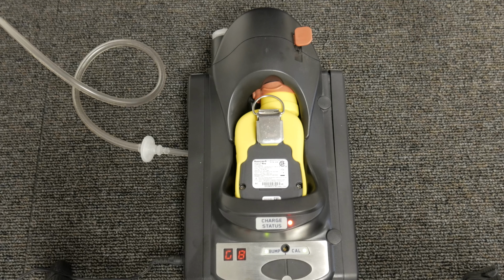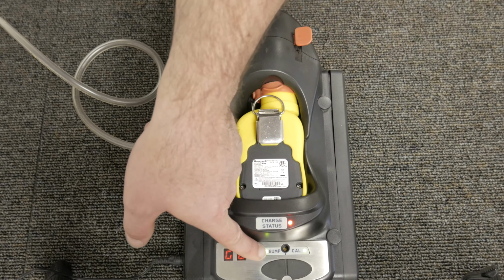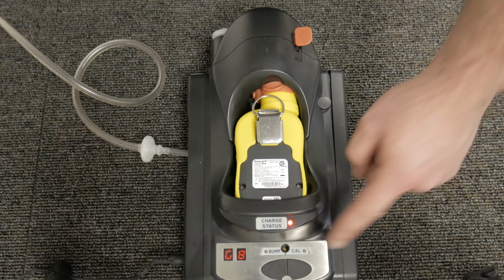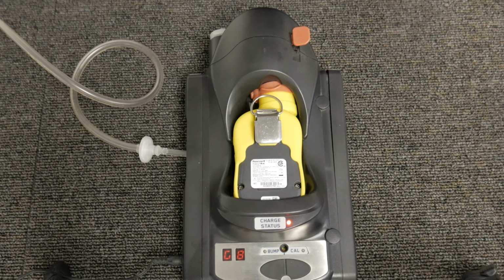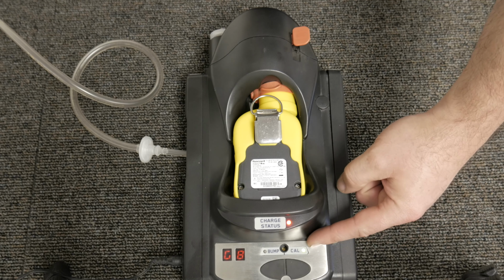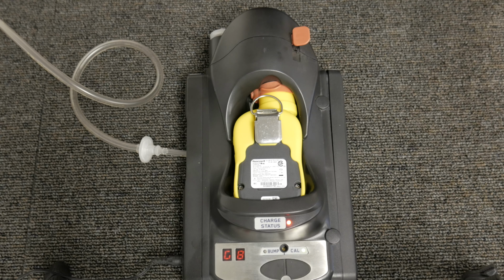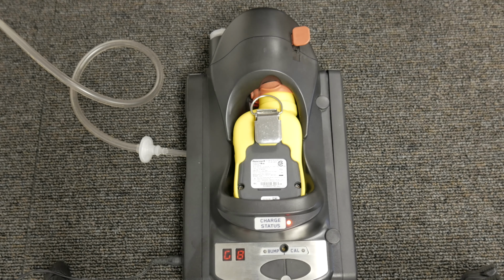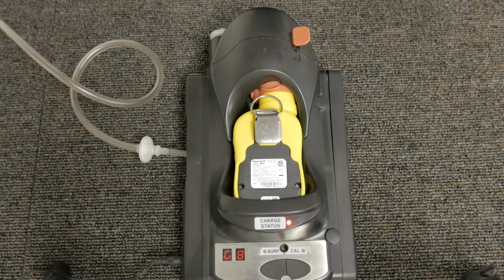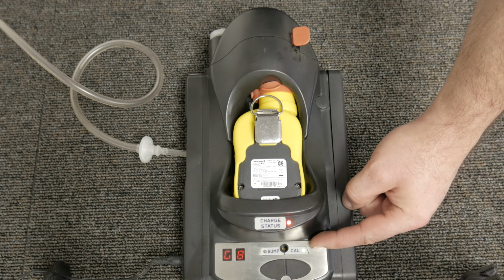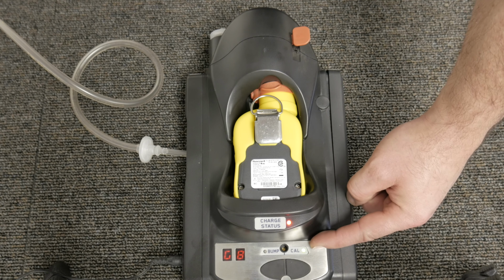And you will notice that the bump light goes away and the cal light is illuminating. This calibration process will take approximately 2 minutes to calibrate the unit for you. You will hear one tone during the process, and that's the unit testing the volume of the buzzer. And then you will also hear 3 beeps, and that will tell you that the unit has passed calibration. When it's passed calibration, it will do a solid green light on the cal.